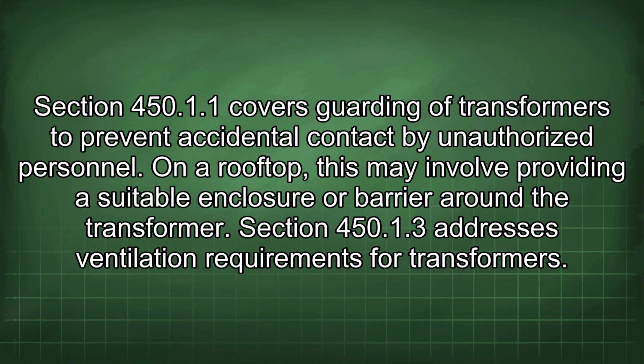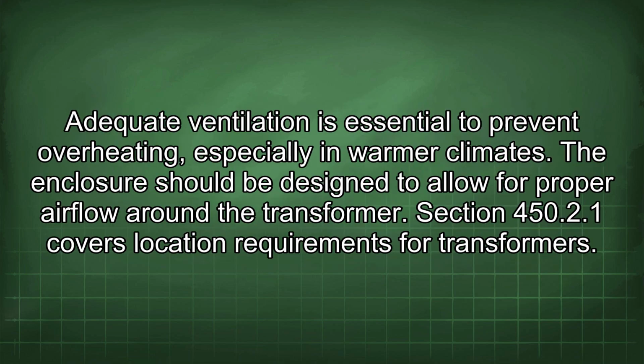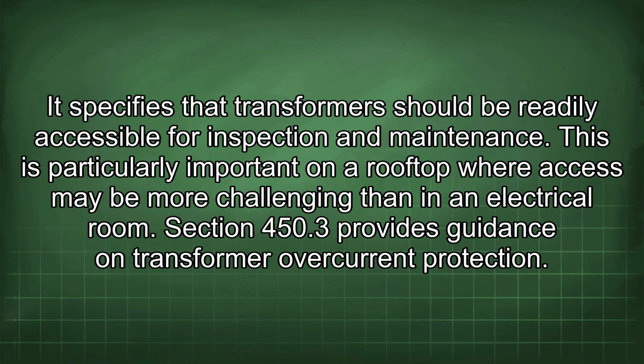Section 450.1.3 addresses ventilation requirements for transformers. Adequate ventilation is essential to prevent overheating, especially in warmer climates. The enclosure should be designed to allow for proper airflow around the transformer. Section 450.2.1 covers location requirements for transformers. It specifies that transformers should be readily accessible for inspection and maintenance. This is particularly important on a rooftop where access may be more challenging than in an electrical room.